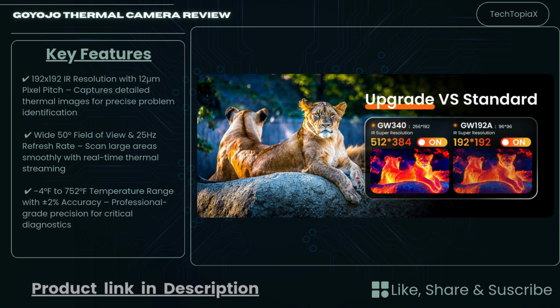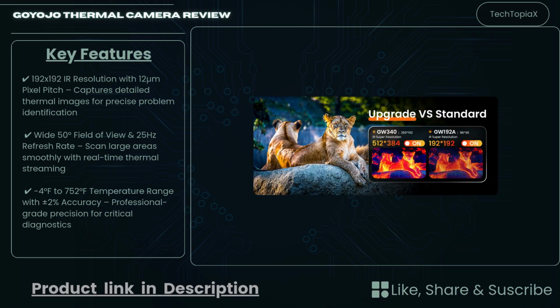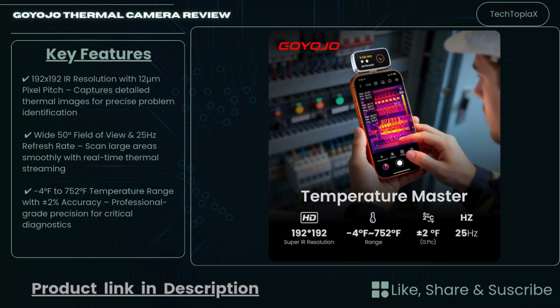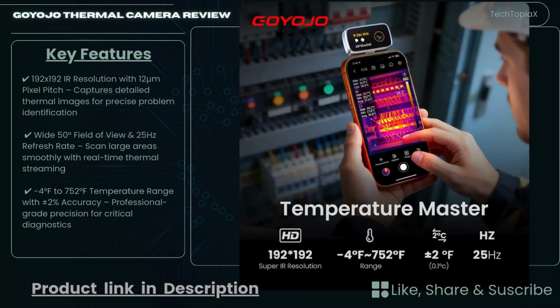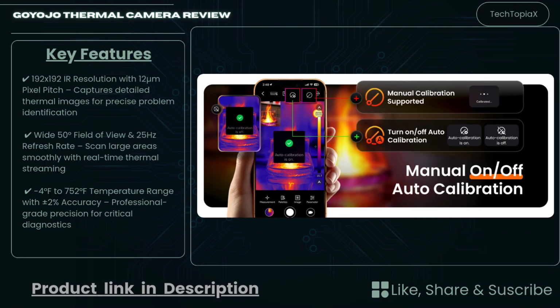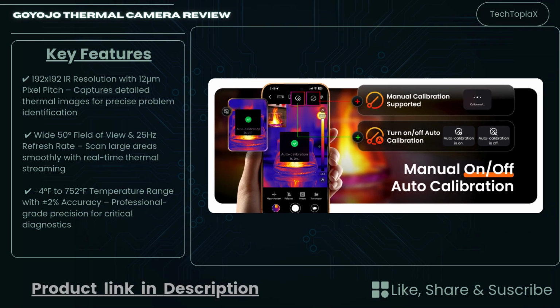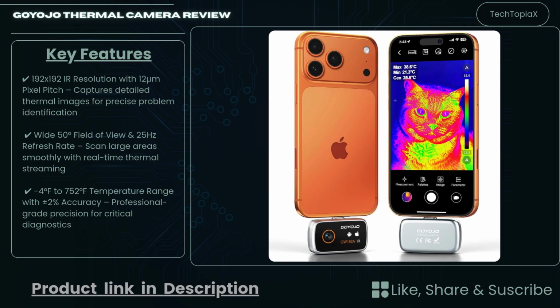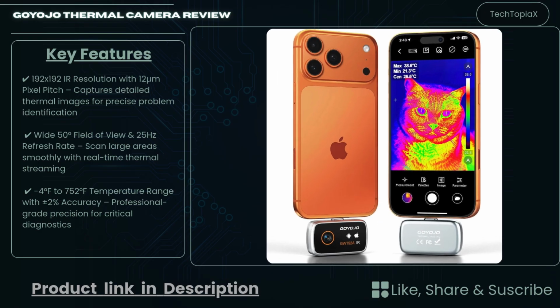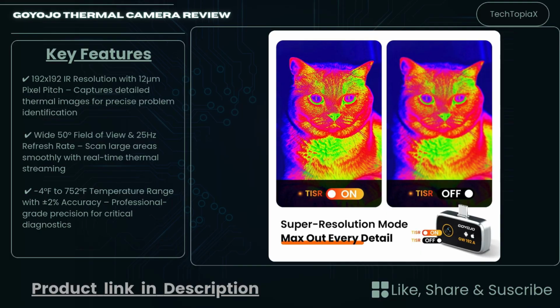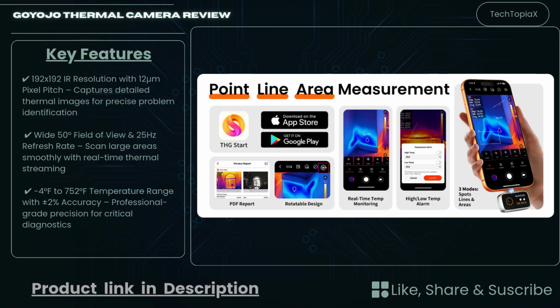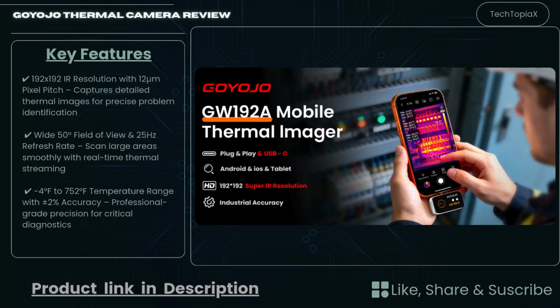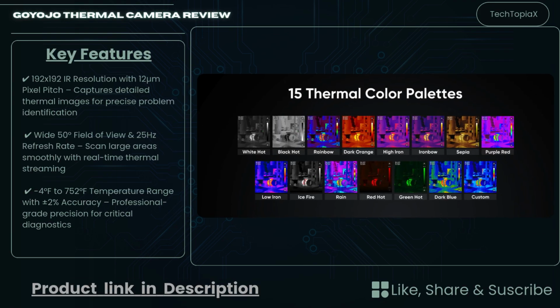Let's talk real numbers. First up, the specs that actually matter. This camera packs a 192 by 192 infrared resolution with a 12 micrometer pixel pitch thermal sensor. What does that mean in real-world use? It means you're getting incredibly detailed thermal images that can spot temperature differences down to the smallest detail. We're talking about a 50-degree field of view, wide enough to scan entire ceilings, floors, and walls without constantly moving around. The 25 Hz refresh rate gives you smooth, real-time thermal streaming, no lag, no stuttering, just fluid imaging.